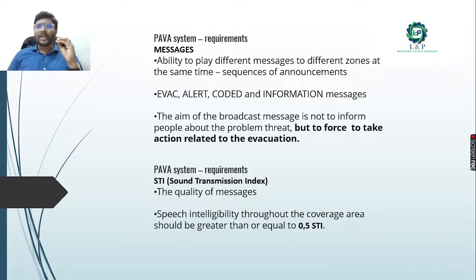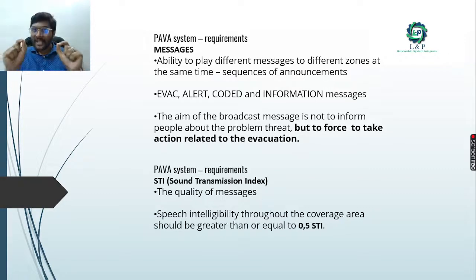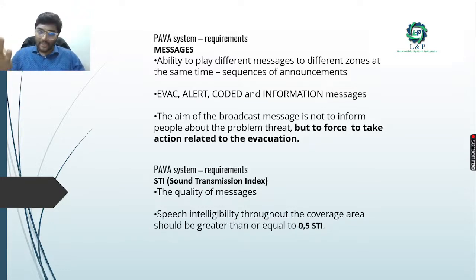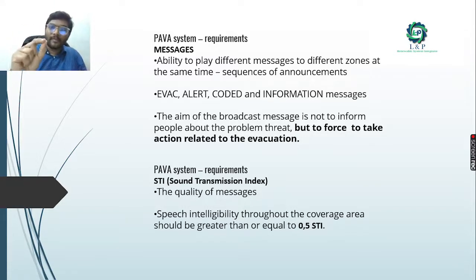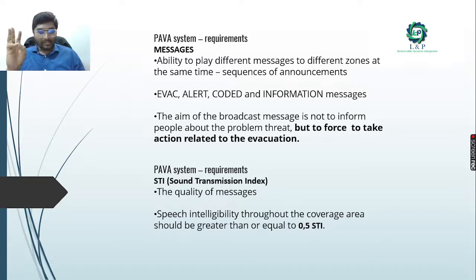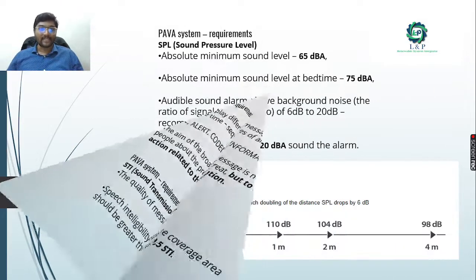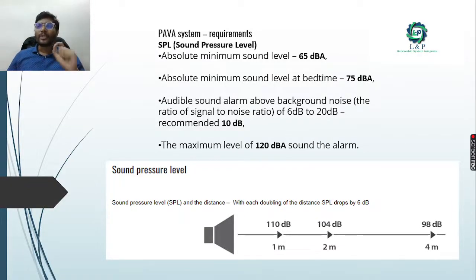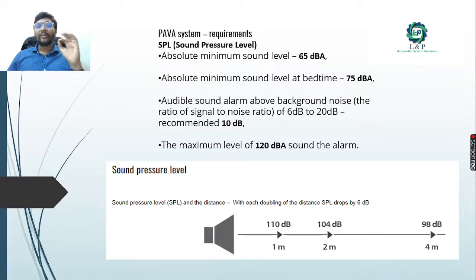The system must have the ability to play different messages to different zones at the same time. Messages can be evacuation, alert, code, or information messages. The aim of the broadcast message is not just to inform people about the problem or threat, but to force them to take action and evacuate. For sound transmission index, the coverage area should be greater than or equal to 0.5. For SPL, the absolute minimum sound level should be 65 dB, bedtime level 75 dB, and the maximum 120 dB for sound alarms.